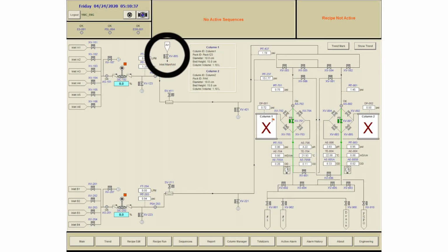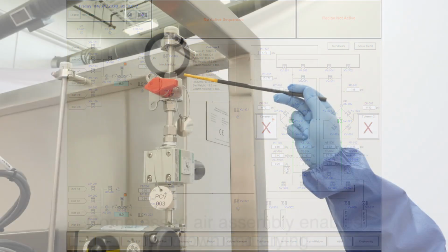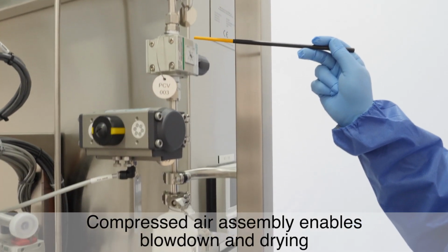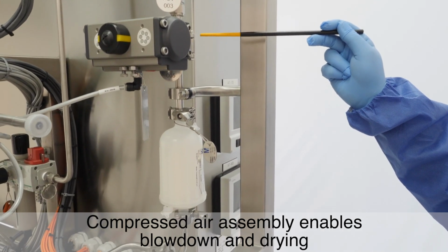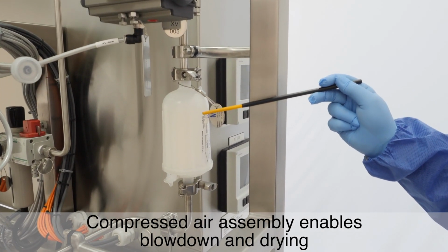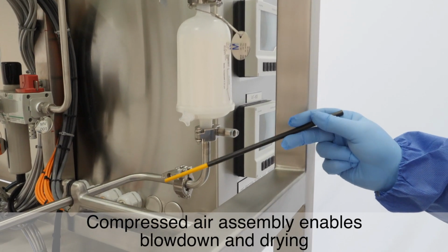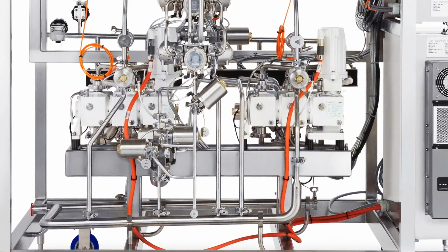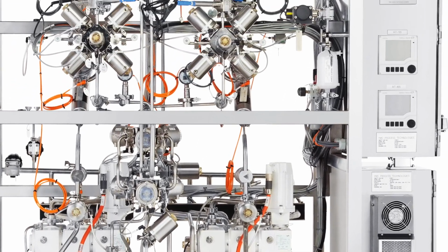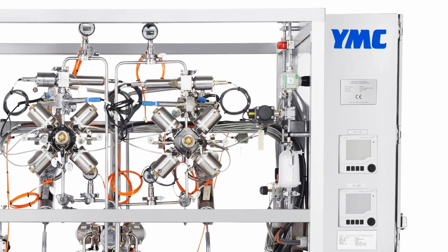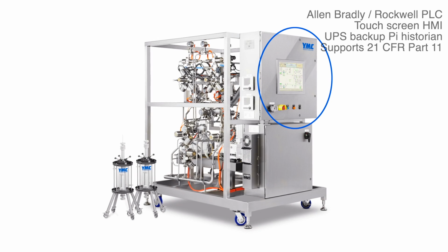Of course, a compressed air inlet is available for blowdown. Here are the actual inlet valve and filter. This line can be connected to the pump inlets to enable efficient blowdown to drain as well as to dry the system. That completes the introduction to the flow path of this ContiChrome Twin 500 system. Let's now take a brief look at the control panel.